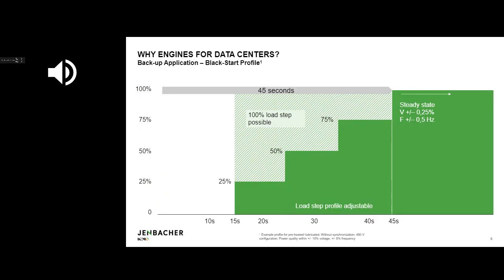Let's go a bit into performance now, to show how we compare on diesel replacement performance. Here you can see an exemplary curve of a G4 performance class on our natural gas engines, where you have a 15-second start - since the command, the engine starts running, gets up to speed, and within 15 seconds you can apply the first load. In this example, we apply a 25% step load, so within 45 seconds you get to 100% load. We can also tailor-make this curve to match your project requirements - even a 100% load step is possible, depending on the power quality you need in terms of voltage and frequency deviation, but basically we can adapt all types of solutions.